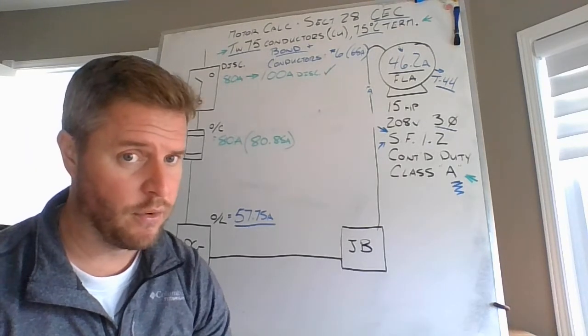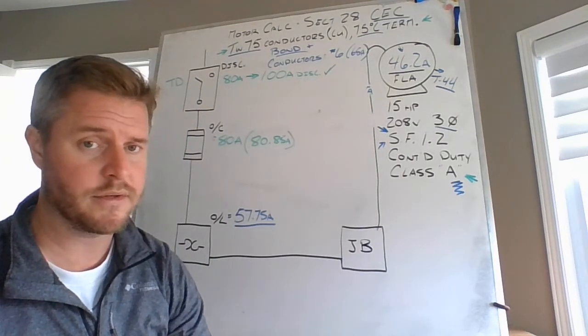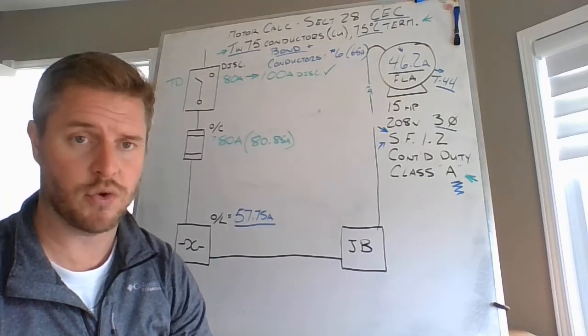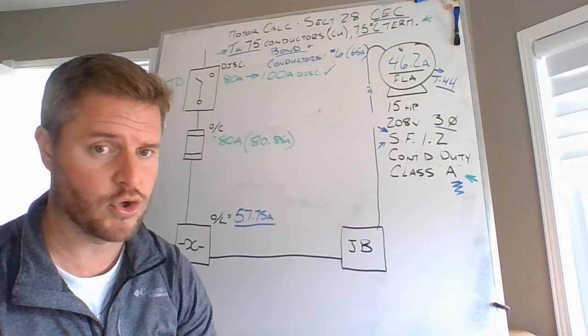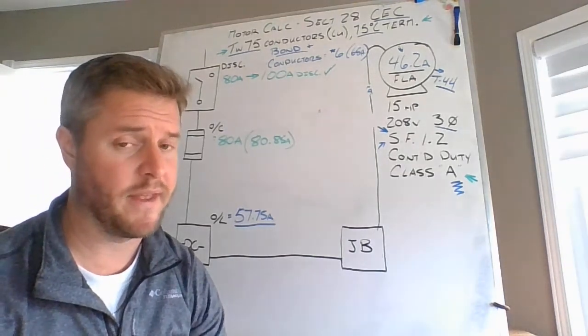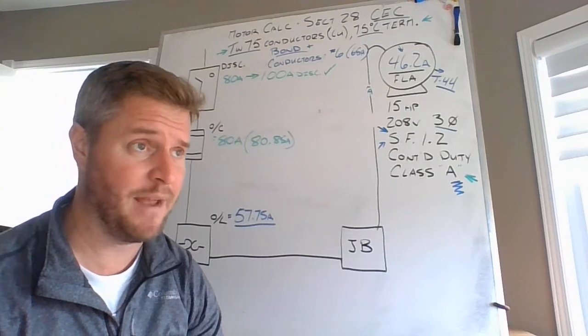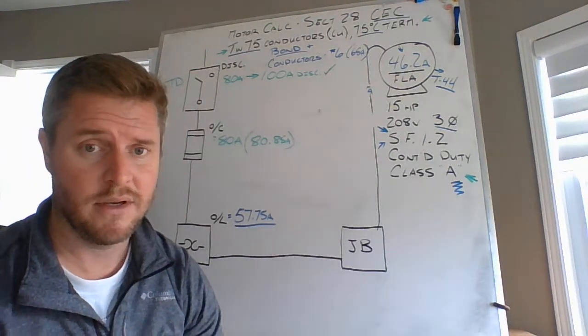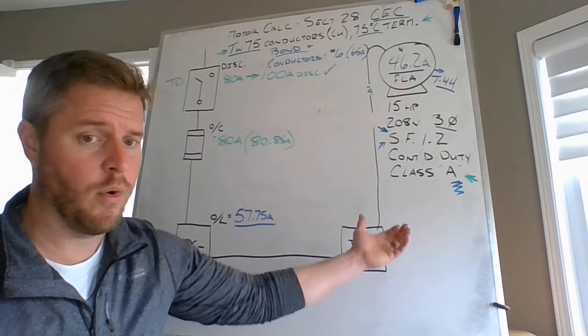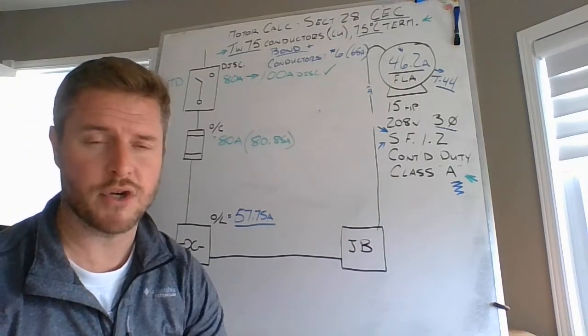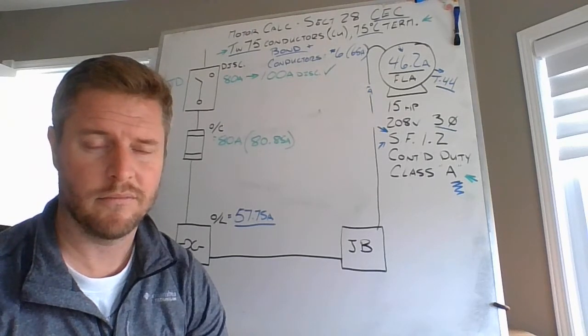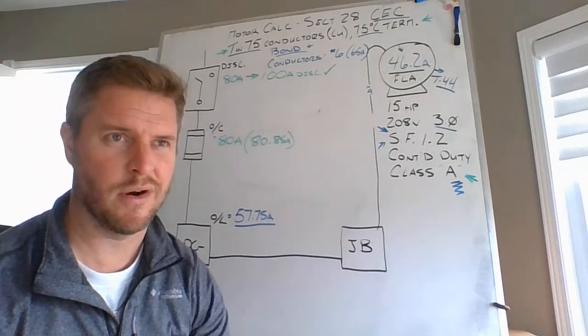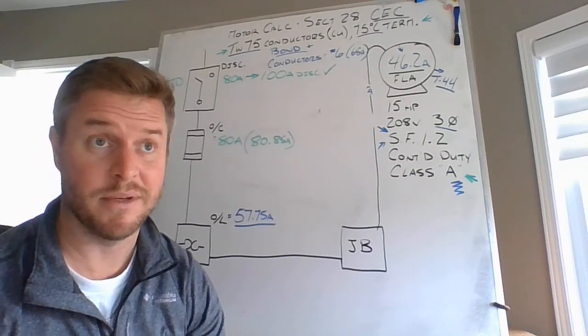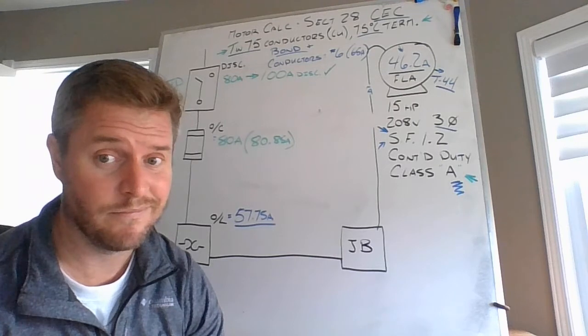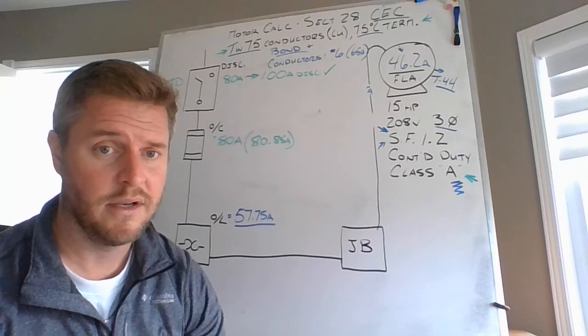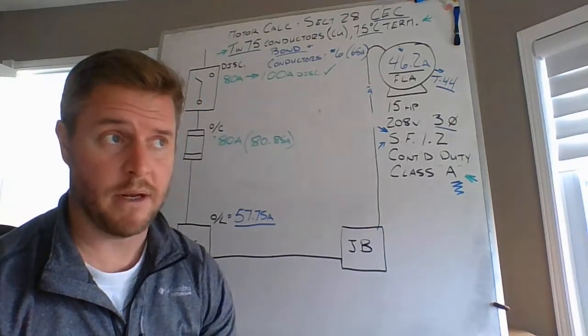So you have to be very careful when you're going through and looking at these different code rules, because we're talking about Canadian Electrical Code section 28 here. We're not talking about industrial motor control. Industrial motor control, I read that excerpt. It also says that you have a 10 amp motor with a 20 amp overcurrent device. Give me one example for what we know right now that would have a 10 amp motor with a 20 amp overcurrent breaker. Breakers are set at 250% of the FLA. That'd be a 25 amp breaker. Like that doesn't make sense. So be very careful with that rule. We'll expand on that a little later on.